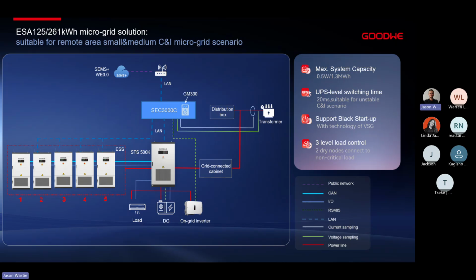We will be able to do a microgrid solution as well, where we can connect 5 of these 125 kilowatt PCSs together to an STS. That STS will then be able to handle all of our switching, and can also handle our on-grid inverters, diesel generator, all of our loads and everything. All of that gets connected to an SEC 3000C controller. So that SEC 3000C controller is the main brain, and that is how we'll be able to supply all of the power in a microgrid solution.